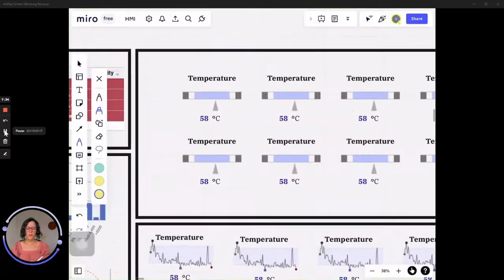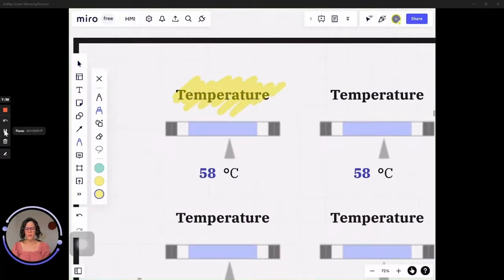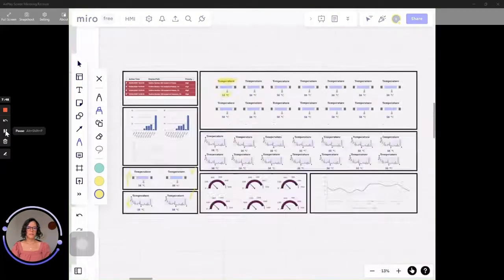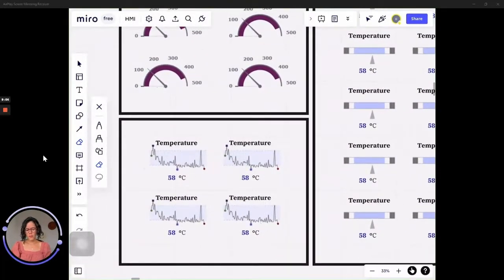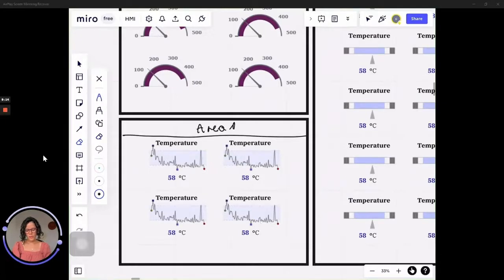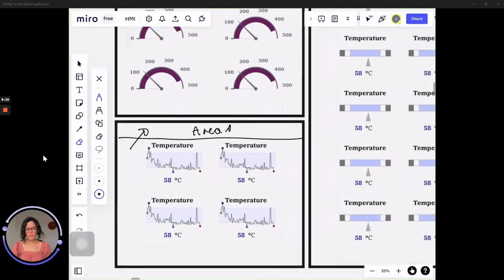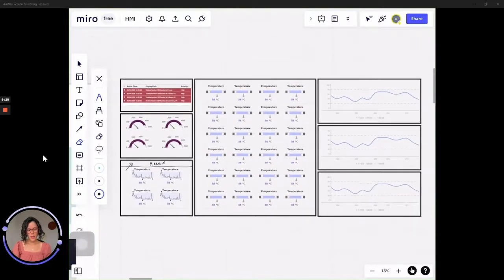Show only the most important information — for example, the name, the process value, and the engineering unit. This will be enough for Display Level 1. It should be easy for the operator to navigate into the process — they can easily navigate into level two, level three or more. What we will do is use headers in the tiles, so when the operator clicks on the header, they can navigate into, in this example, the level two of this area. We will make headers in all the tiles so the operator can navigate into different process areas or information.